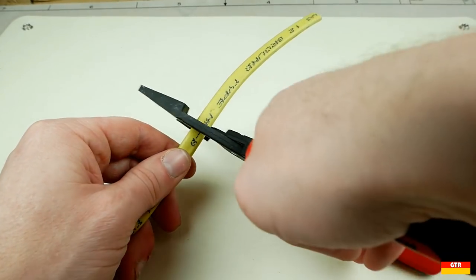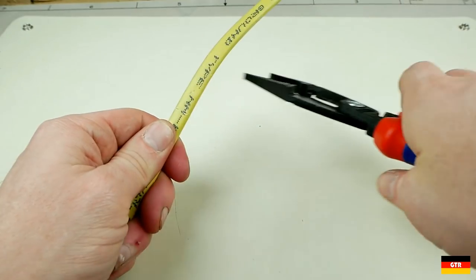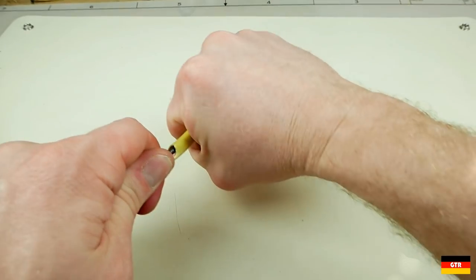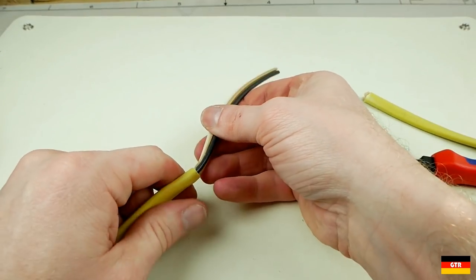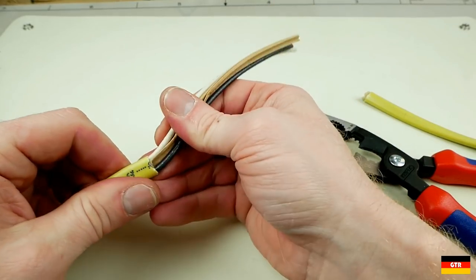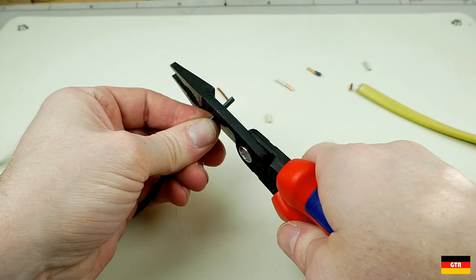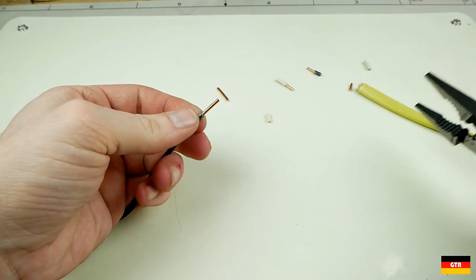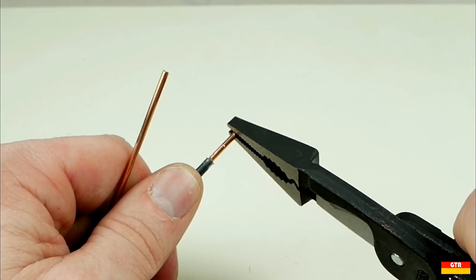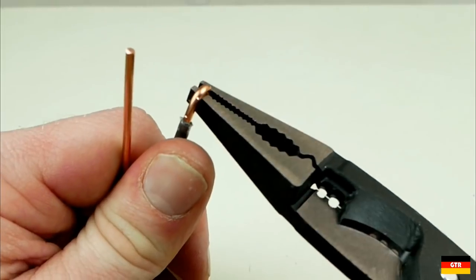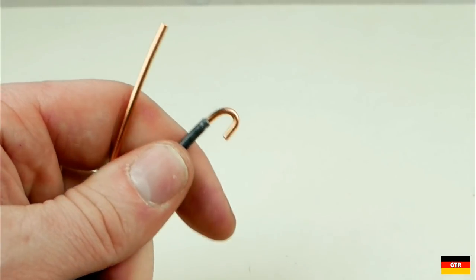You could use the cable cutters to score the outer jacket material. I'm not sure if this would be recommended though because the curved nature of the blades makes it much more likely to damage the inner insulation but you can certainly do this in a pinch. Using the cable strippers I had no problem on the insulation of these cables. It did leave a small mark on the conductor but I believe that is typical for this style cable stripper when using solid conductor wire.